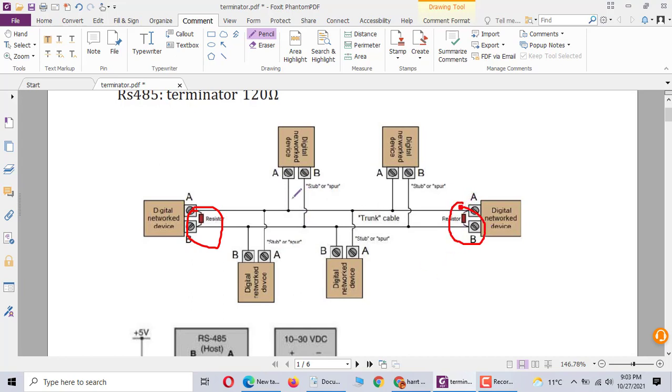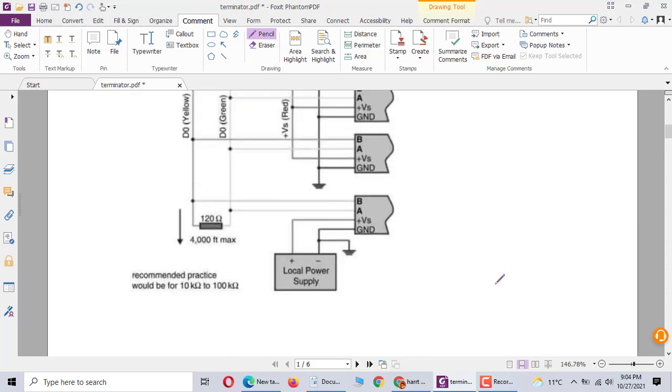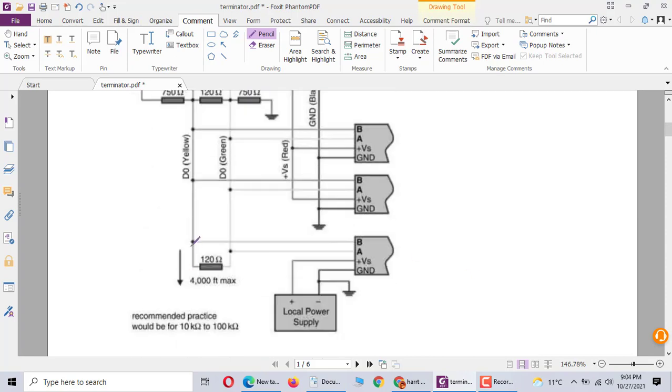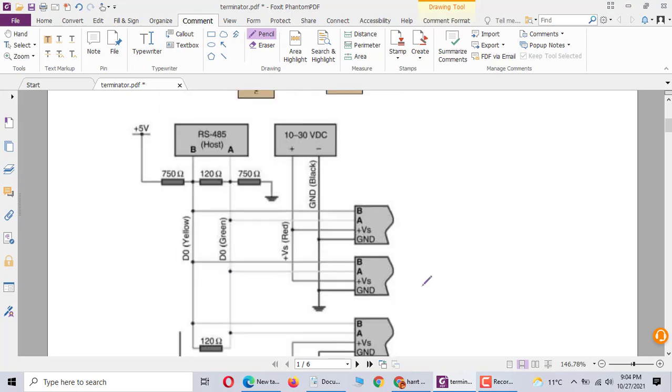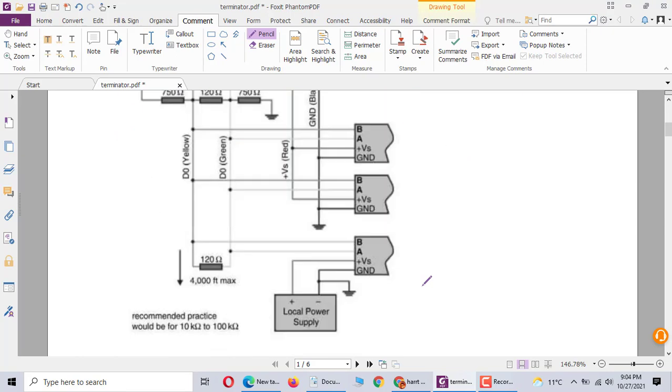On the last device you can have a termination resistor, but in the middle device you can't do anything. You can't use the resistor. This host one is 120 ohm. The last one, this is the trunk cable, the last one is 120 ohm. This is RS-485.